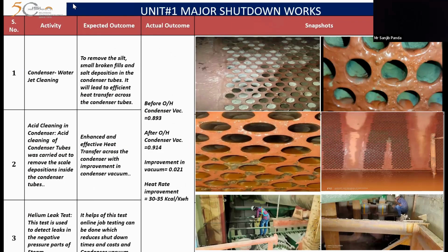Condenser water jet cleaning we have done. Air acid cleaning in the condenser we have done. Helium leak detection and all this to recover the condenser vacuum, which was initially 0.893, and we have achieved up to 0.914, a gain of 0.021. Which has given us 30 to 35 kilocal per kilowatt hour improvement in heat rate. Next one.